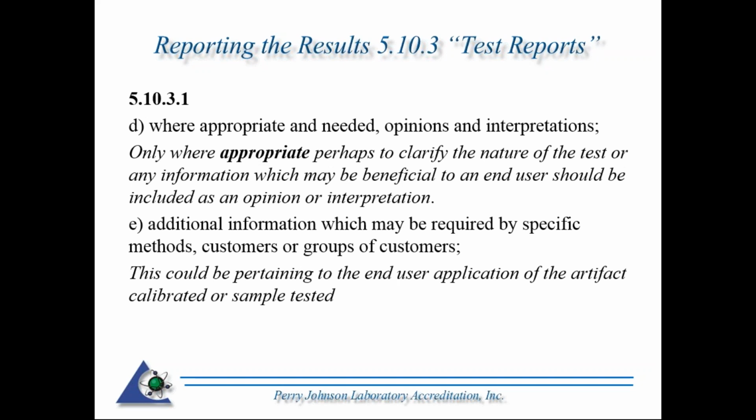Where appropriate and needed, opinions and interpretation. Again, only where appropriate, and that's the way it's stated in the standards. Only where appropriate, perhaps to clarify the nature of the test or information which may be beneficial to the end user, should be included as an opinion or an interpretation. E, additional information which may be required by specific methods, customers, or group of customers. And again, this could be pertaining to the end user application of the artifact calibrated or sample tested.